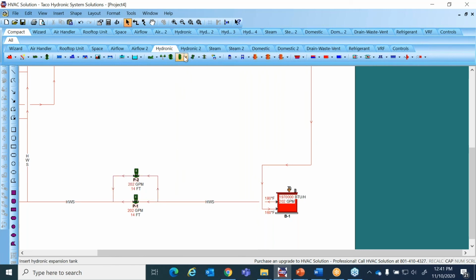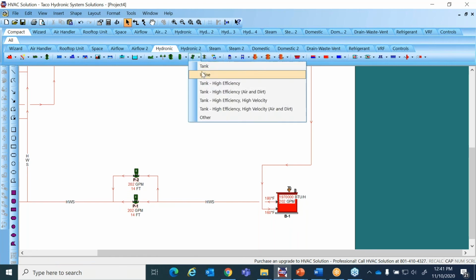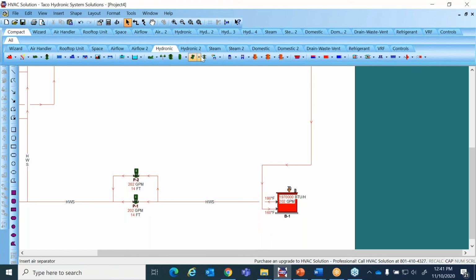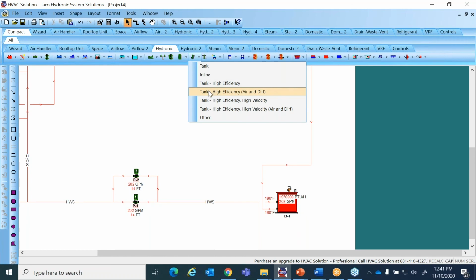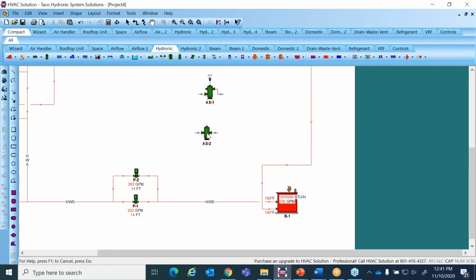Then I'm going to get an air and dirt separator. You folks may be used to the vortex-type picture, where it goes in high, swirls around, and comes out low. But really, talk to your TACO rep, or go online, or sit in on an air and dirt separator presentation—consider specifying the inline ones instead. The piping's easier, and they're a lot more efficient at removing air and dirt, which helps us all install a better system.